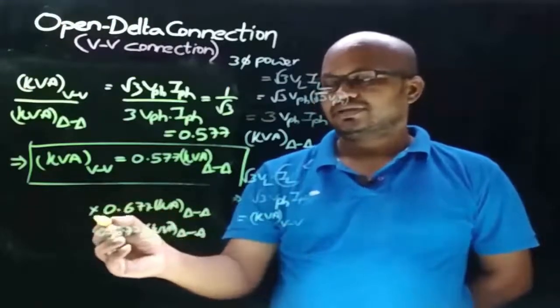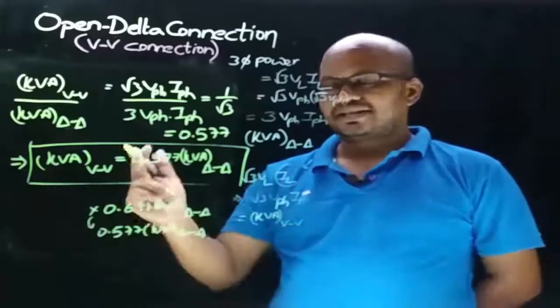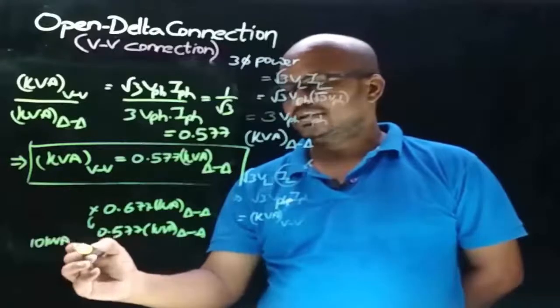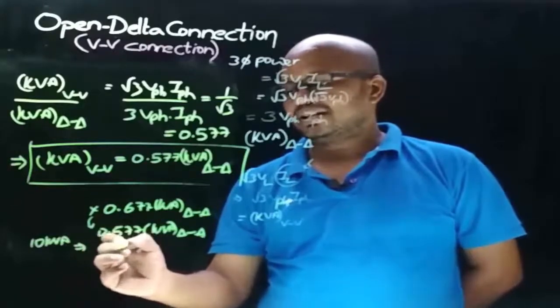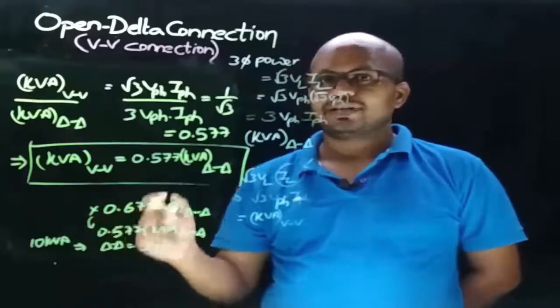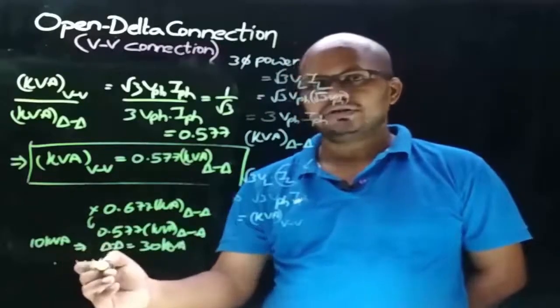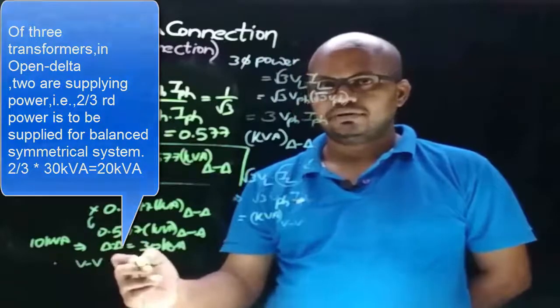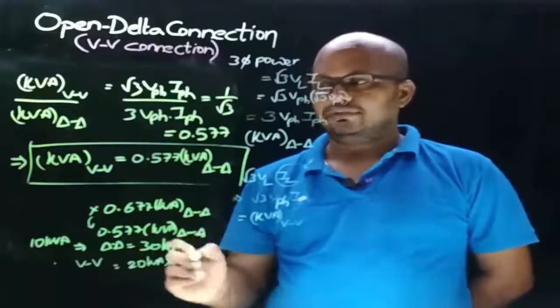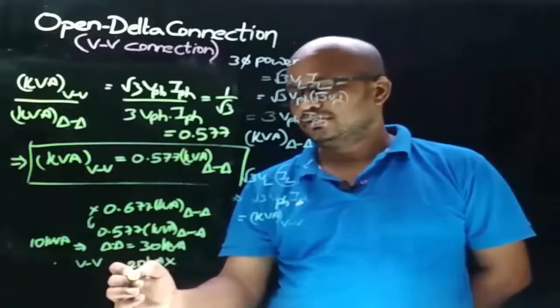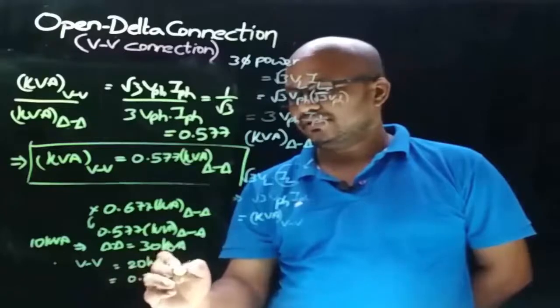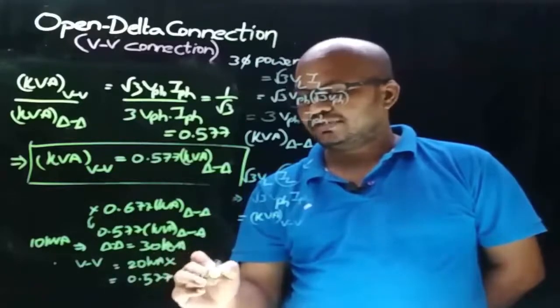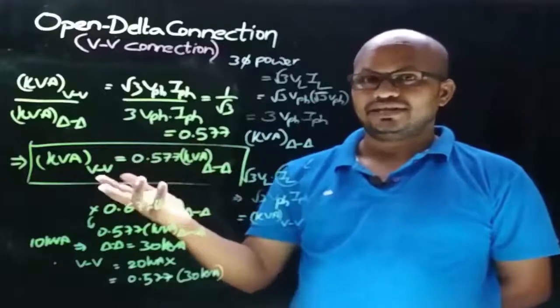Let's understand this with an example. Let the rating of each transformer be 10 KVA, so the power delivered by delta-delta connection is 30 KVA. When one transformer fails, we might think the power delivered by open delta connection is 20 KVA since two transformers are involved, but this is not true. With open delta connection, the power transferred is 0.577 times the delta-delta rating of 30 KVA.